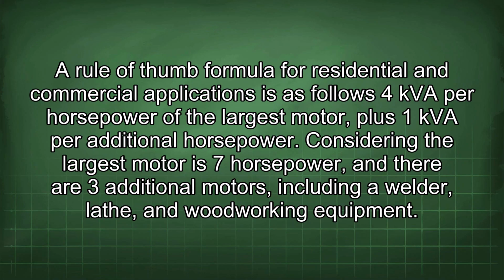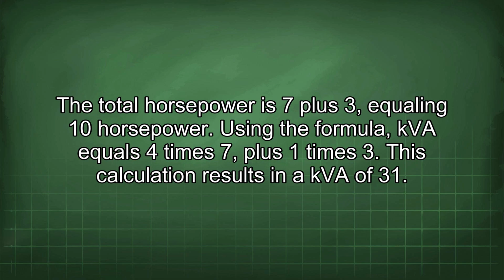A rule of thumb formula for residential and commercial applications is as follows: 4 kVA per horsepower of the largest motor, plus 1 kVA per additional horsepower. Considering the largest motor is 7 horsepower, and there are 3 additional motors, including a welder, lathe, and woodworking equipment, the total horsepower is 7 plus 3 equaling 10 horsepower.